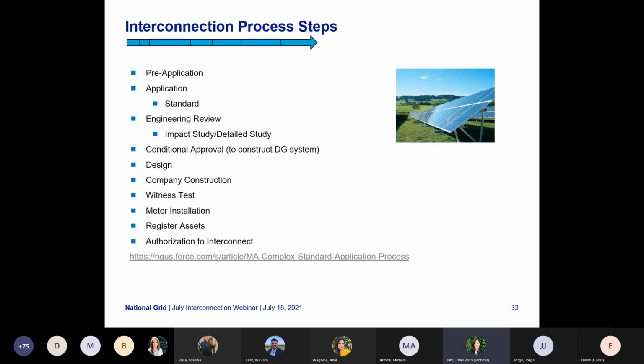Next slide. So the process steps in the standard process would be pre-application and then application, which at that point will determine it's a standard project, and then engineering review, which would be the impact study, as well as a detailed study if applicable, and then conditional approval, which will be the step to have the ISA drafted and executed. And then once payment is made, then we'll go into design, and then company construction, witness testing, meter installation, registering the assets, and then ATI.